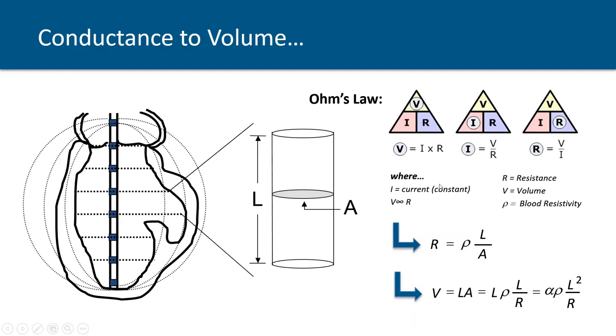Now, if we blow up one of these segments, we indicated that they're modeled as cylindrical discs, basically just stacked up inside the left ventricle. The resistance for each of these cylinders is provided by electrical theory of a conductor, and it's related to the resistivity of the material inside that cylindrical disc. Could be blood, could be saline, and this is multiplied by the distance between those electrodes and divided by the cross-sectional area of that segment. The volume of this cylindrical segment is simply L times A, and if we substitute from the above equation into this, we have the fundamental equation for converting a volume to a conductance.